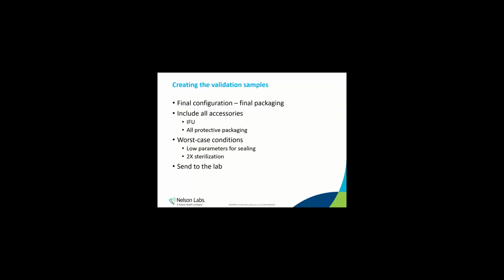Well, let's review. We made our plan by selecting appropriate test options and a statistically valid sample size and wrote it all up in a validation protocol. Then we may have done some family grouping and worst case justification to reduce our testing burden. And now we're ready to start testing. This is a good time to talk about making samples. As we learned earlier, samples should be in the final configuration and final packaging with all intended accessories, including the IFU and protective packaging. We want to make these validation samples in a worst case condition to add more robustness to the validation. This includes using the low parameters for sealing and a 2x worst case sterilization. Now it's time to send them to the lab.